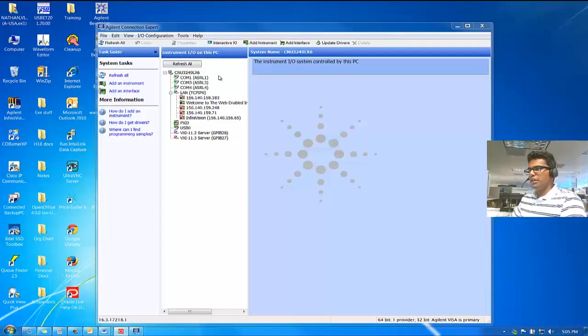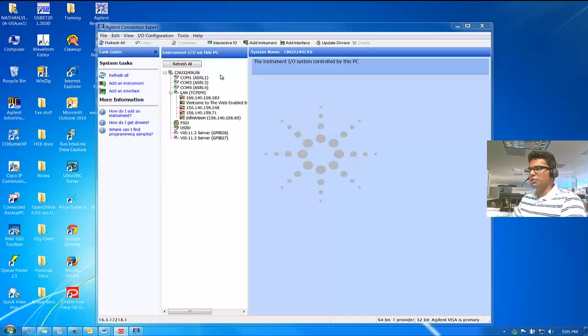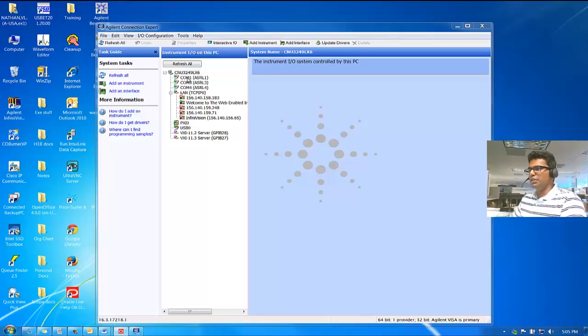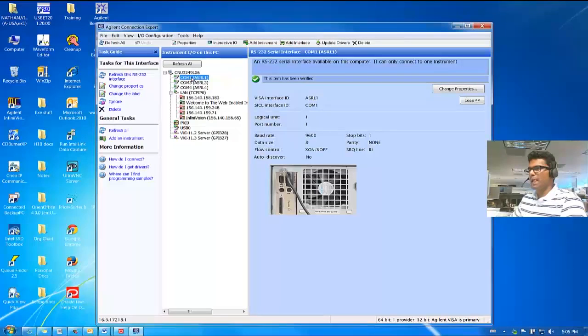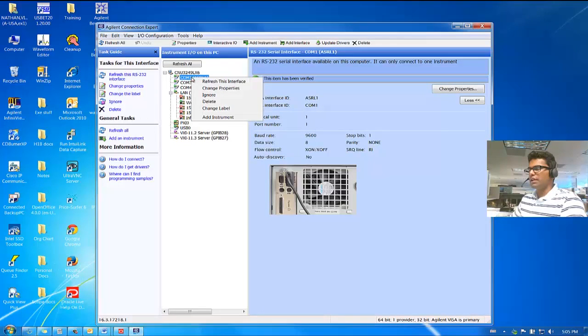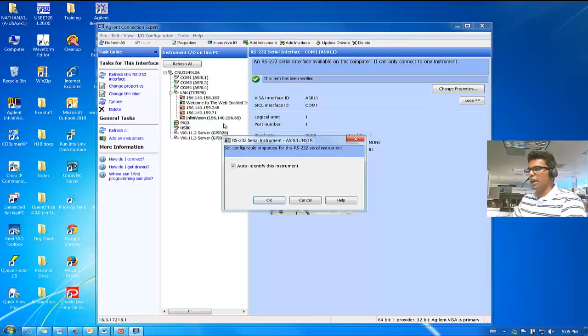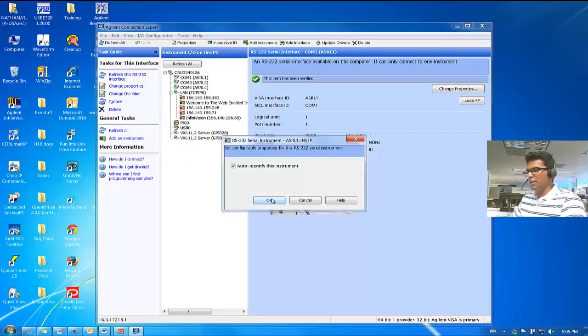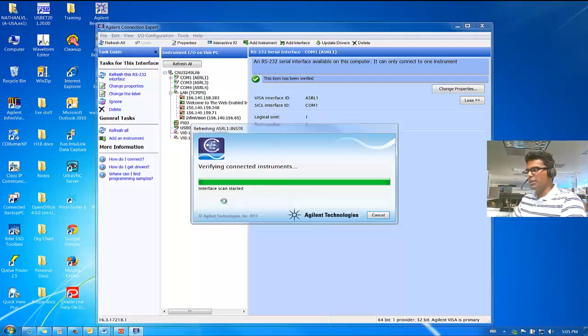Now, once the Agilent Connection Expert window is open, at the very top, this is your computer name, and to connect to the 34970A, you will click on COM1, right-click on it and click on Add Instrument. You can leave it as auto-identify. Click OK.